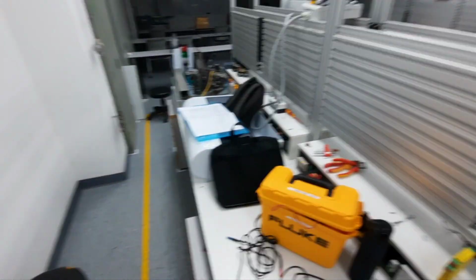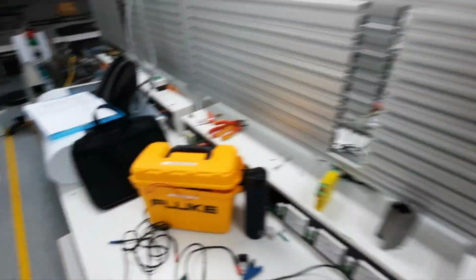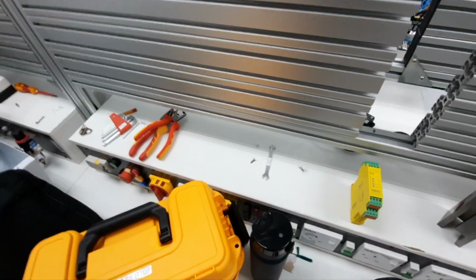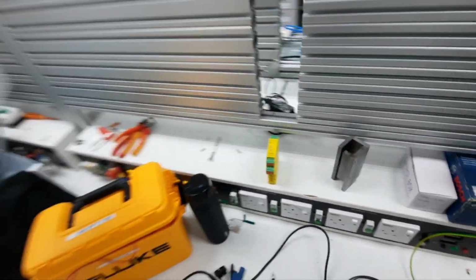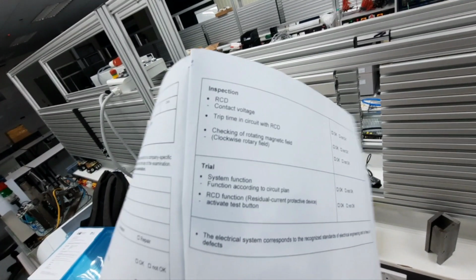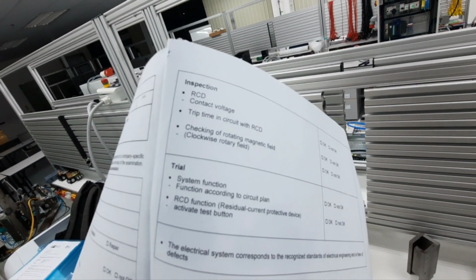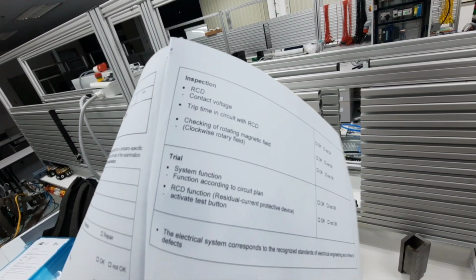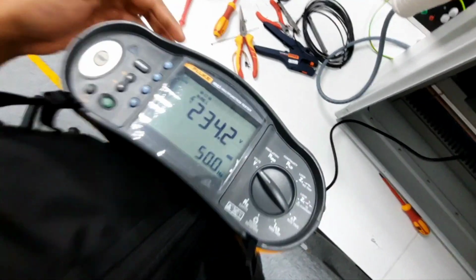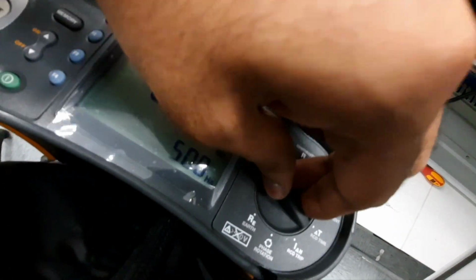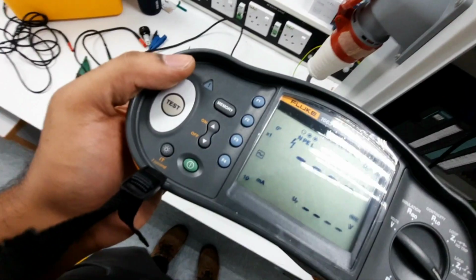Now they ask in the staging list, okay, break the staging. So in your staging list, it says about contact voltage and trip time in circuit in RCD. So if you want to try with the trip current also can. So how to do this? You have to switch it to RCD time.